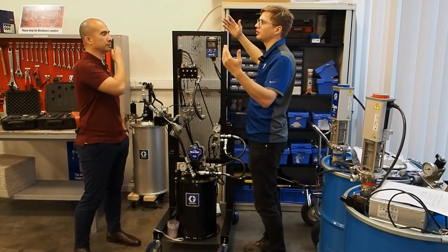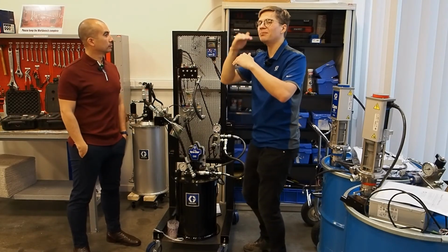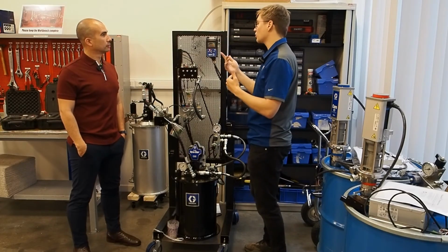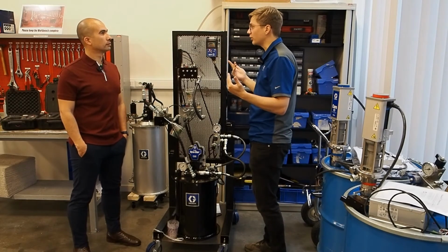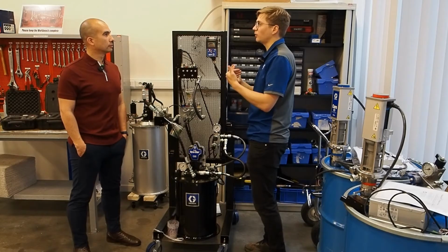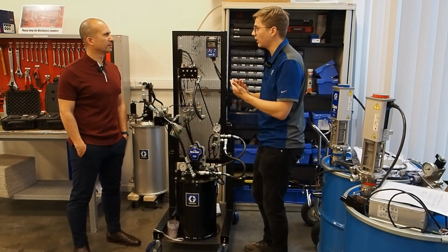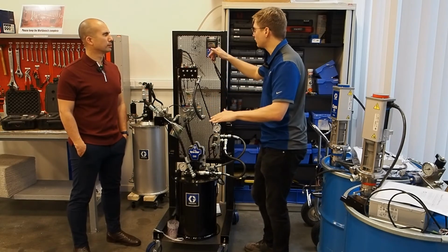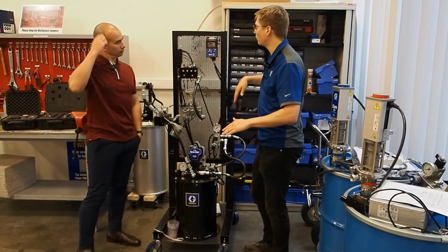There is something happening in the system where the pressure is being built up, but not enough. And that's also the problem of debris potentially in the system, because I cannot build up pressure. Because if you cannot build up pressure for the X amount of time, the system stops. I mean, it gives you low pressure, the system gives a fail mode.